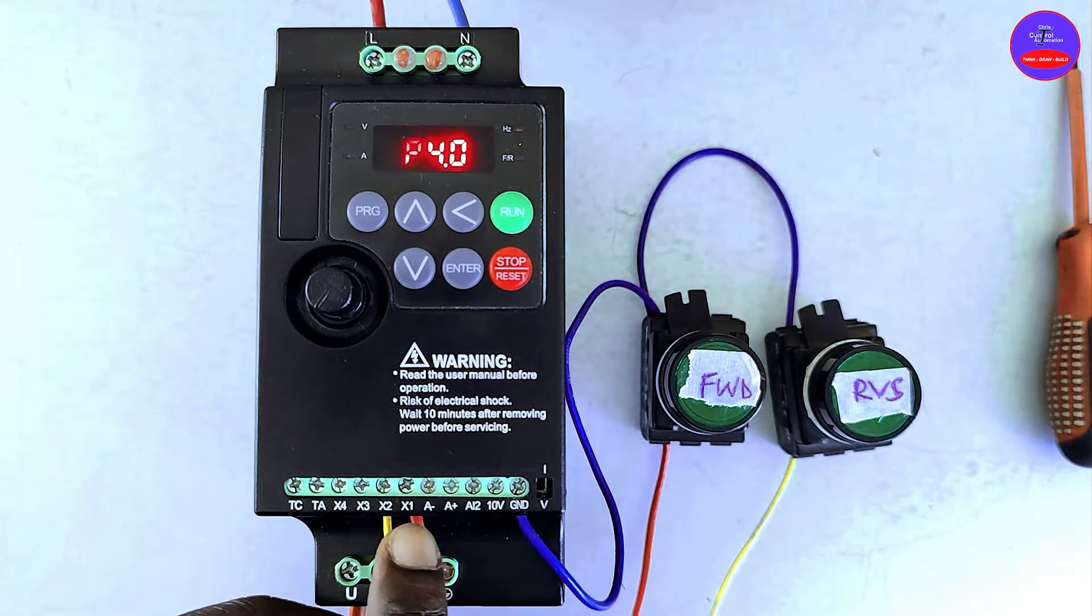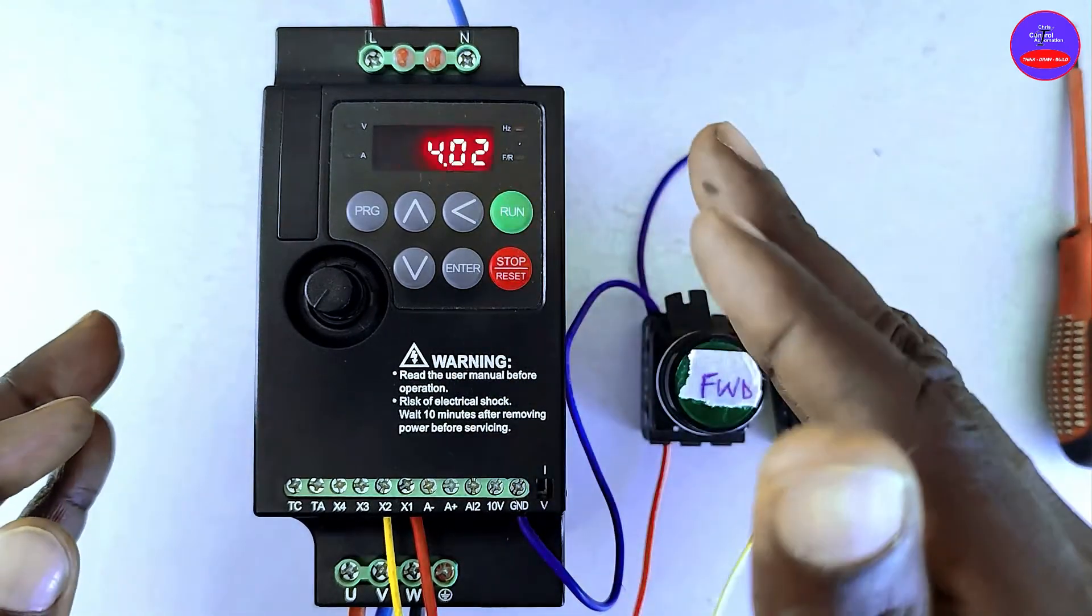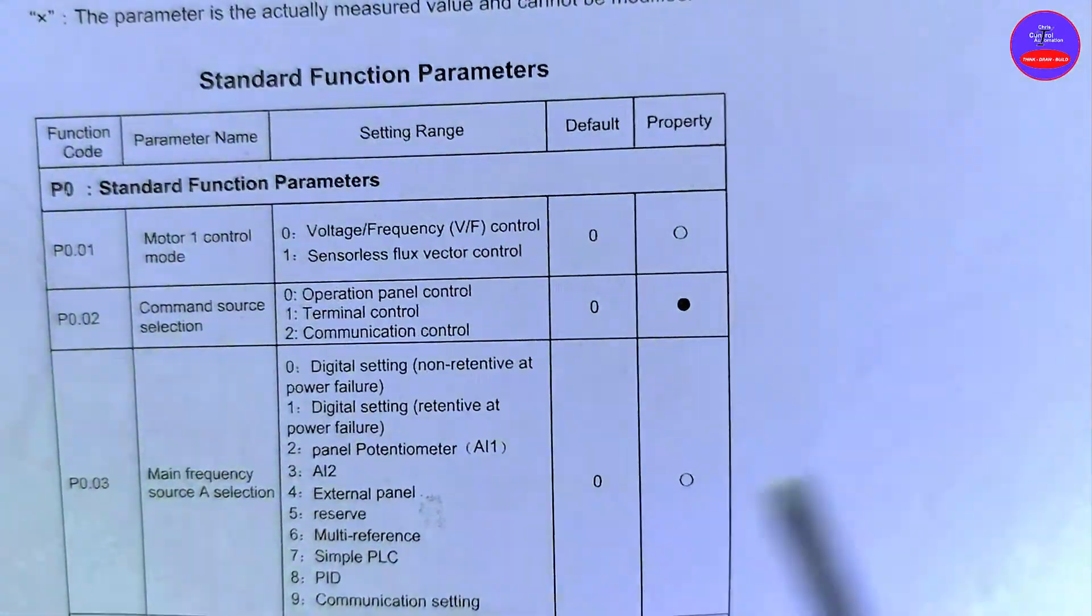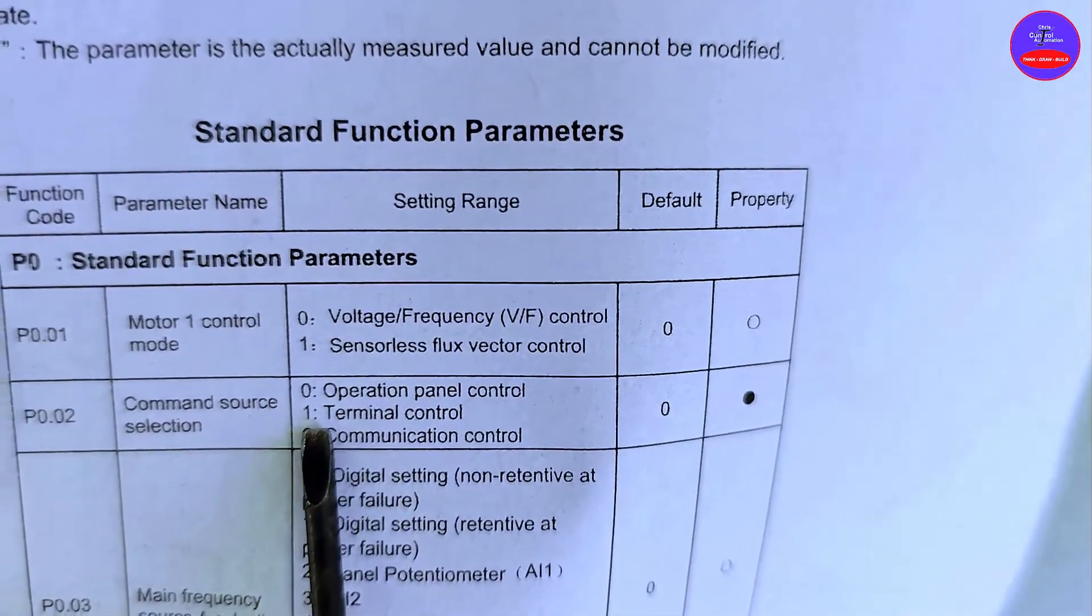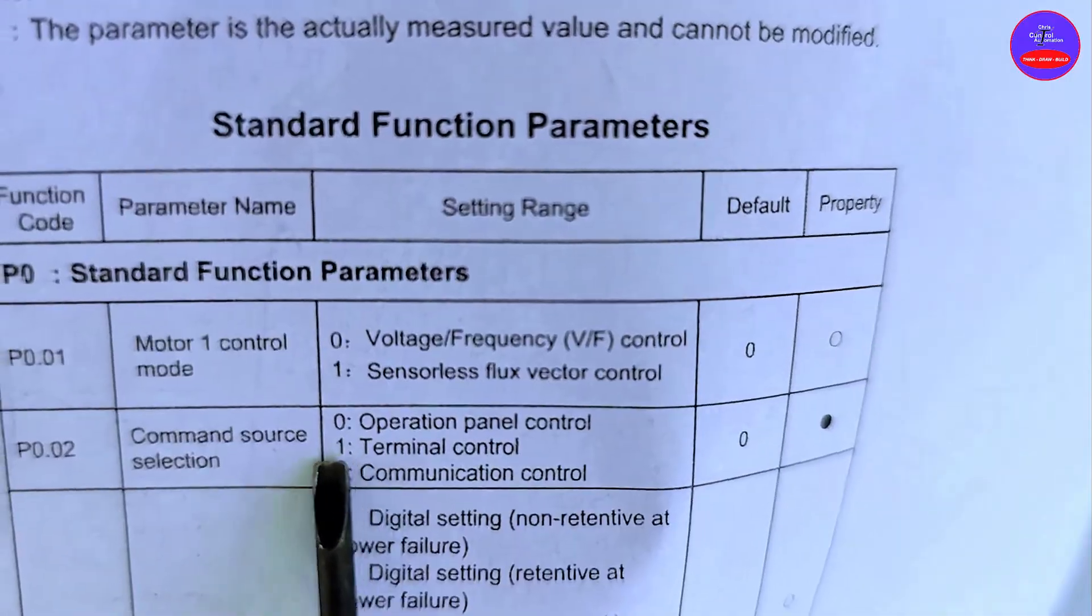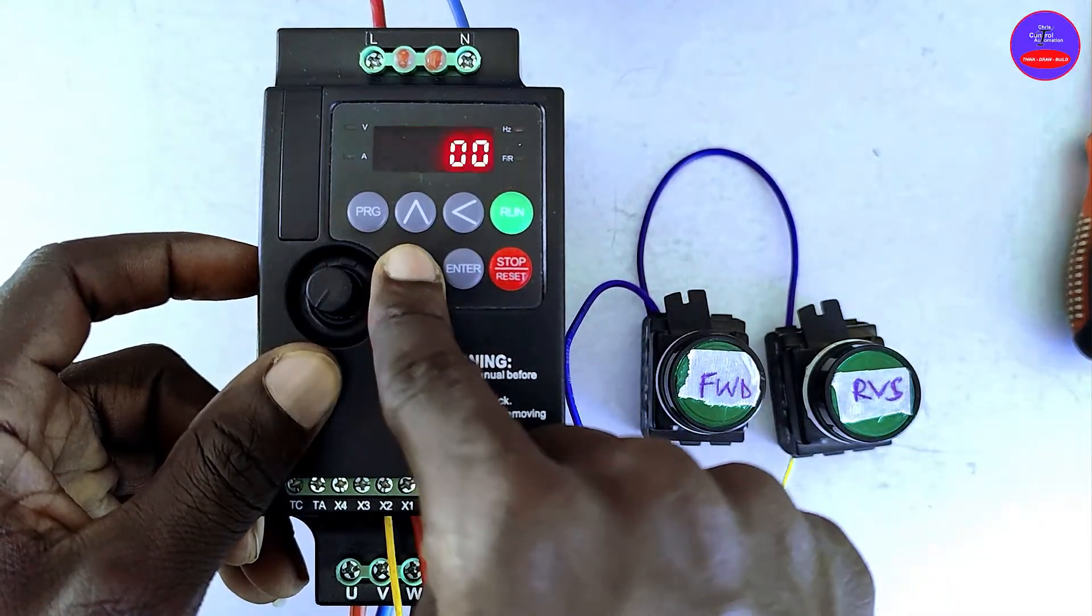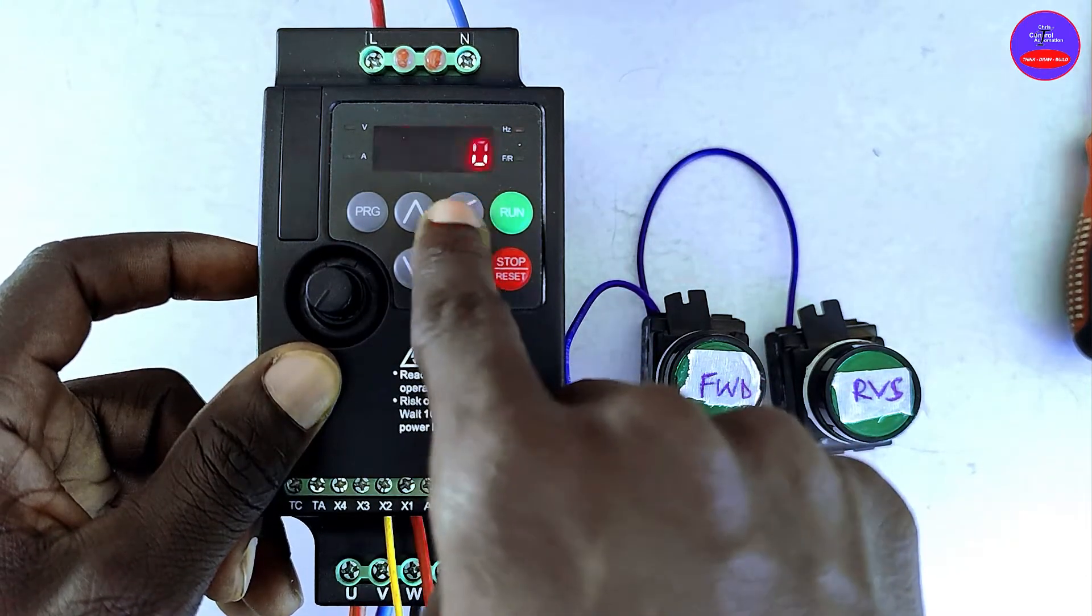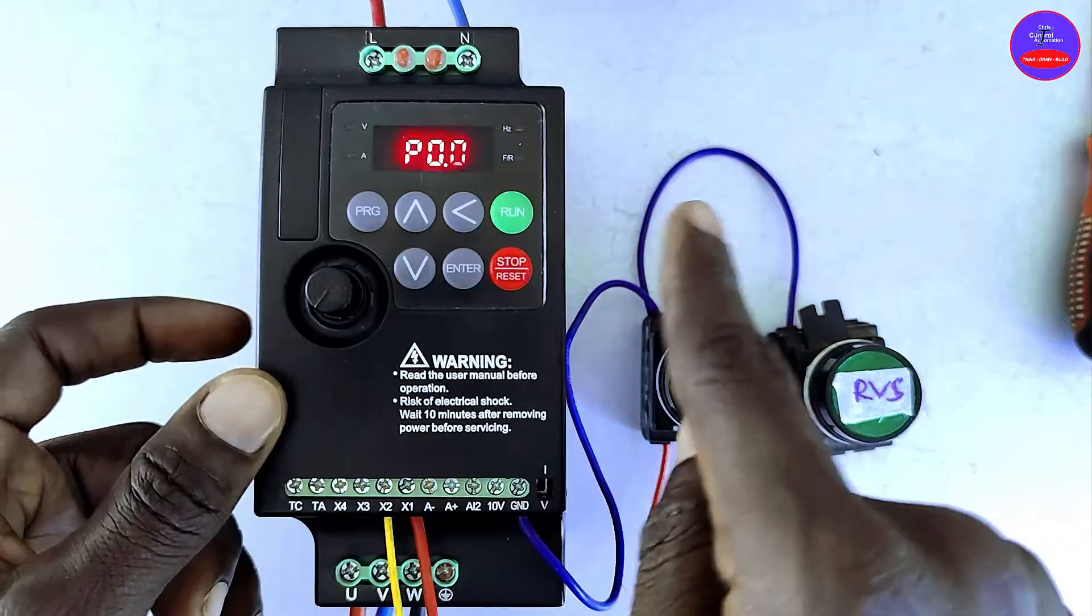Now we are done with the X1 and X2 configurations. We are going to select the type of operation or control. We are going to select terminal control. On this diagram we have command source. Zero is operation control, one is terminal control. So we are going to select P0.02 and choose terminal control. Enter. Now it is already on one. We press enter. Go back.